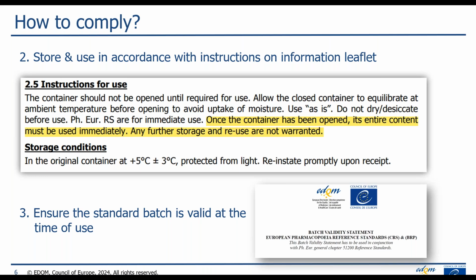Also important to consider the storage conditions. Most of the EDQM reference standards require storage conditions between 2 and 8 degrees. But of course, it's important to check this specifically for the standard being used. And we would follow up on this during the inspection. We would check the data for the fridge, for example, and perhaps the qualification of it as well, if we have time.